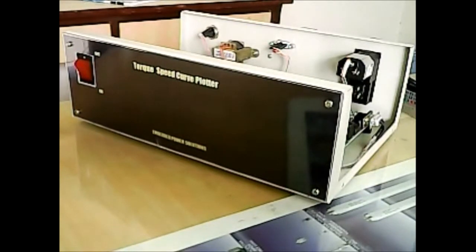So, as we have seen, this complete testing takes hardly a few minutes and the motor consumes a small amount of energy to overcome losses. It also allows taking readings of torques at all the speeds, saving much valuable energy which is dispensed during measuring at full load in conventional testing. We will now demonstrate the software part of the instrument and how to use it.